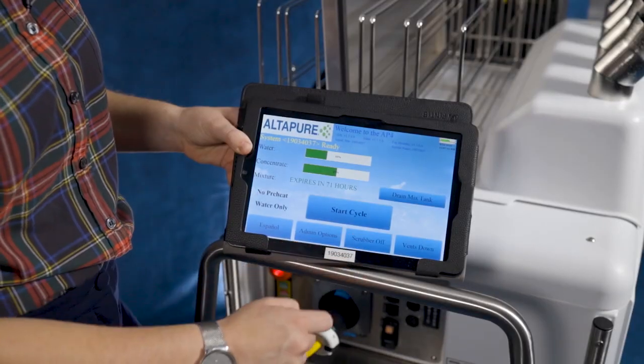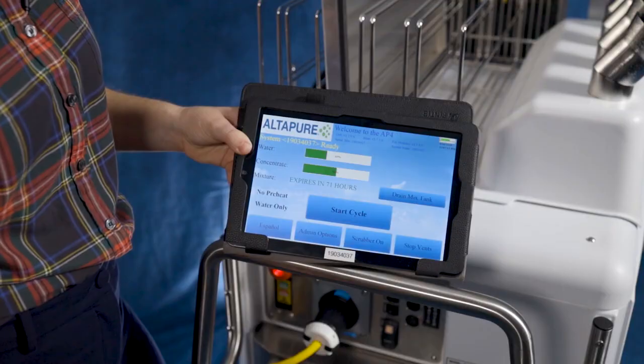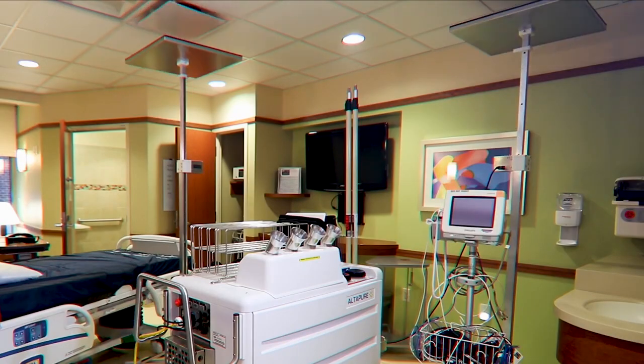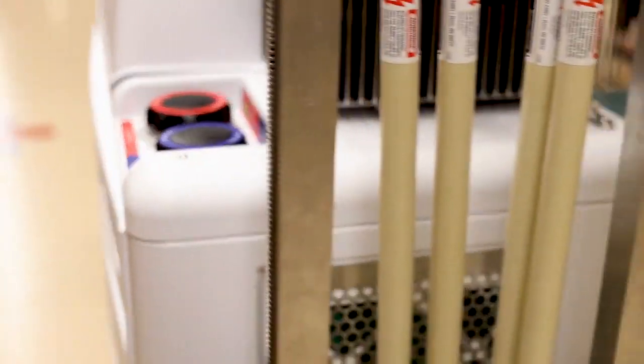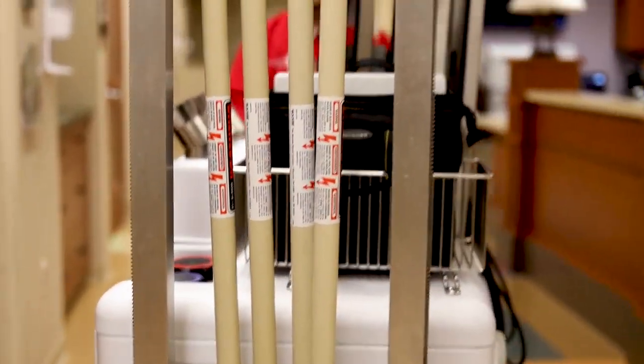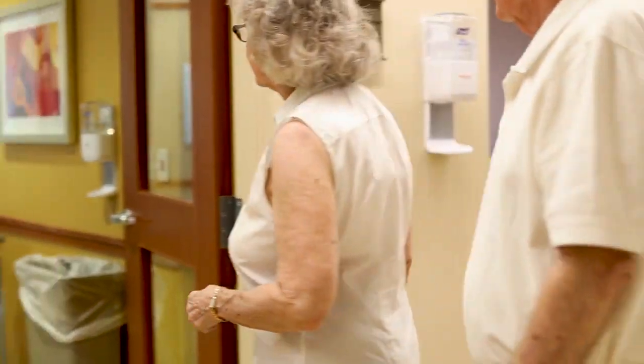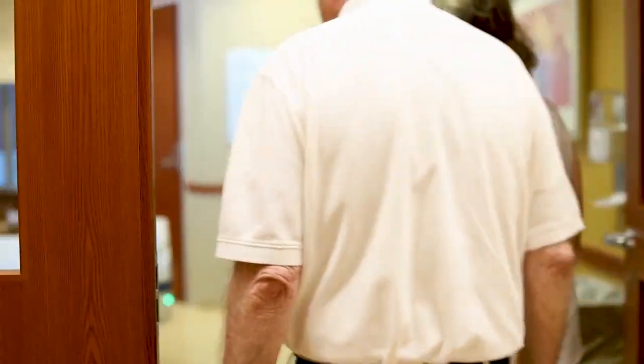On the tablet, press Scrubber off and vents down. Be sure that nothing is in the way of the vents as they lower. Return the room to normal setup for patient. Make sure everything is back on the machine and unplugged and remove the system from the room. The room is now free from pathogens and ready for patient entry.